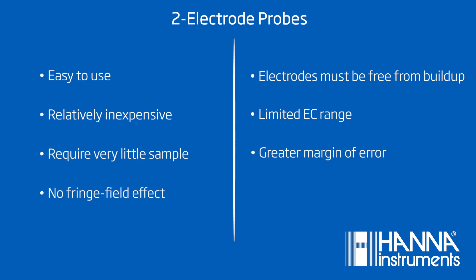So why would you choose one probe over another? What are the upsides or downsides to the technology? Let's go through that now. Two-electrode probes are easy to use, relatively inexpensive, require very little sample to get an accurate reading, and you don't have to worry about the fringe field effect. Don't worry, we'll go over what that is in a bit.